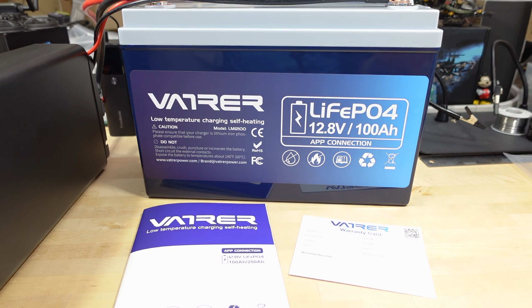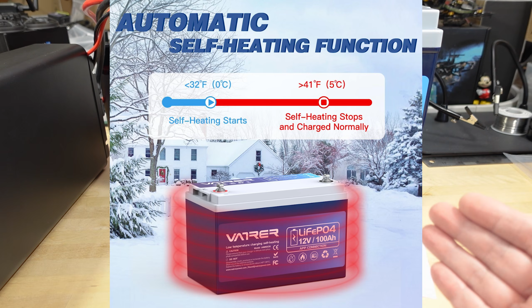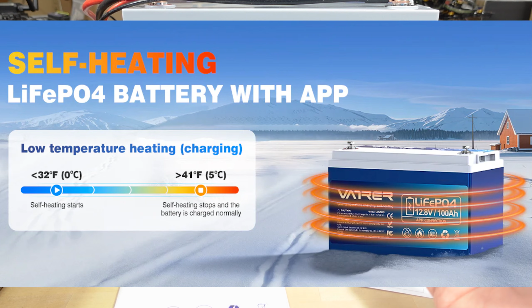It's the low temperature charging self-heating ability. So when this battery detects the temperature falls below 32 degrees Fahrenheit, which is freezing, there's an actual mechanism inside the battery that will self-heat it and warm it back up to about 41 point something degrees. At that point it shuts off and allows the battery to charge. That's very important because lithium iron phosphate chemistry is very sensitive to low temperatures. It doesn't do well in freezing temperatures. In fact, if you attempt to charge the battery when its temperature is too low, close to freezing or below, it can not only damage the battery, it can permanently kill it.